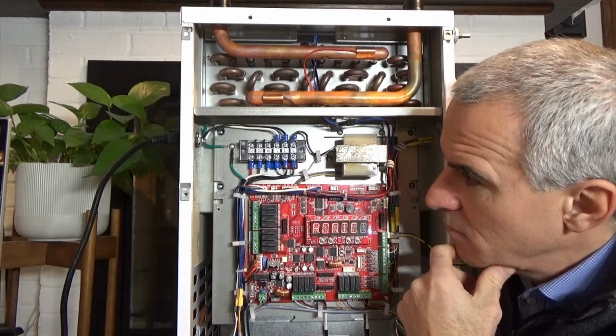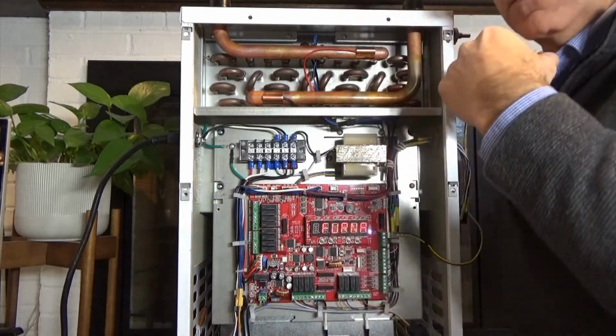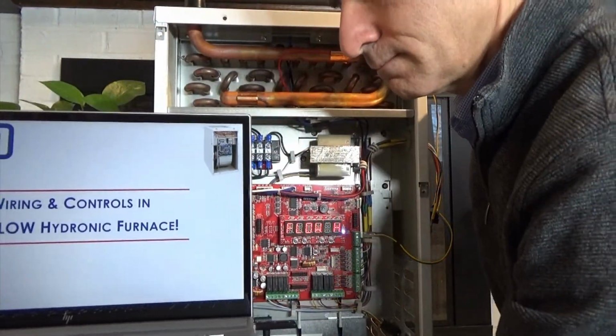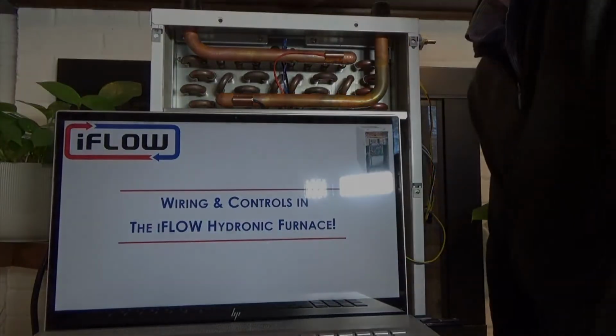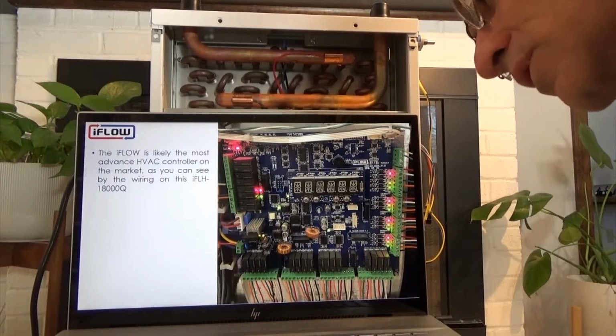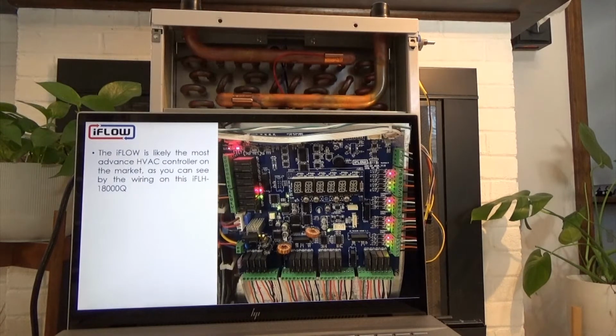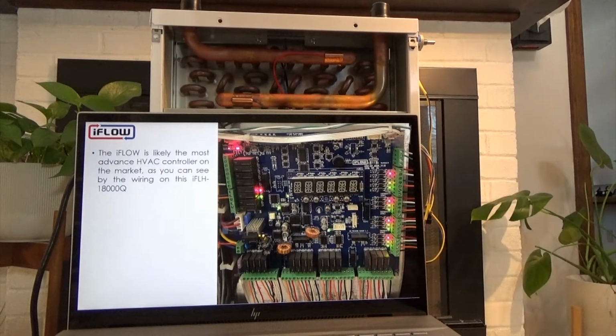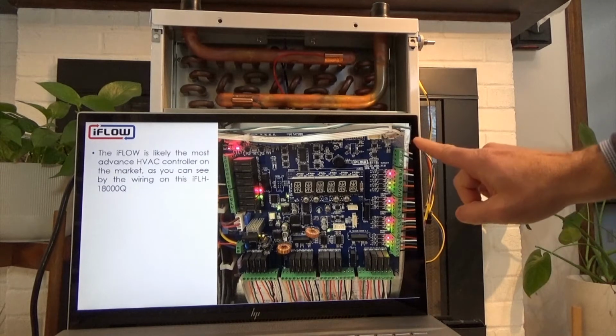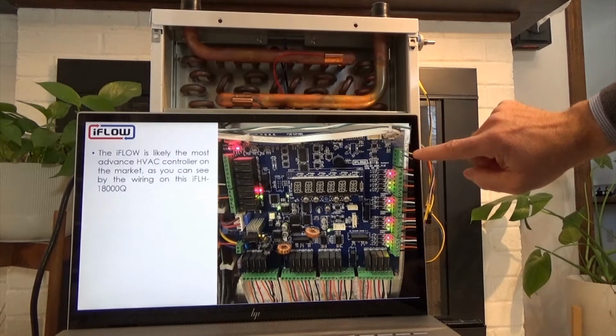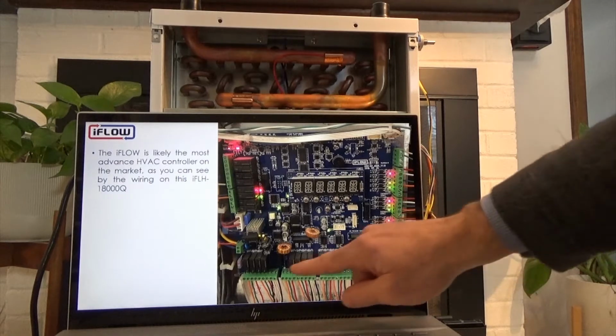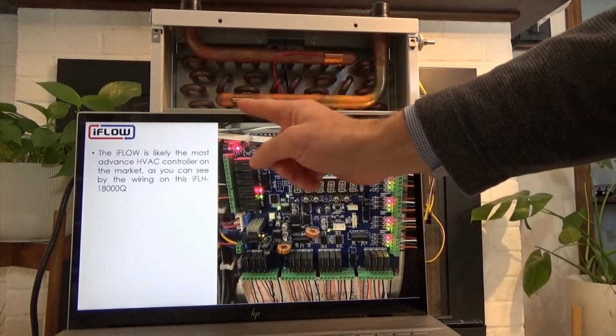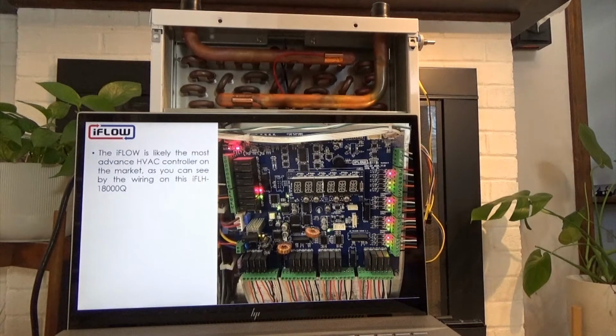So let's look at them in a little bit more detail. For that, I'm going to slide the computer in. The iFLOW is likely going to be the most advanced HVAC controller that you see. You can see by the wiring of this 18,000 unit, that's our 4-zone system, you can see all the wiring. We have our outdoor sensor, we have 4 zones of wiring, we have 4 zones of dampers, and then we have some of our outputs on the left side.